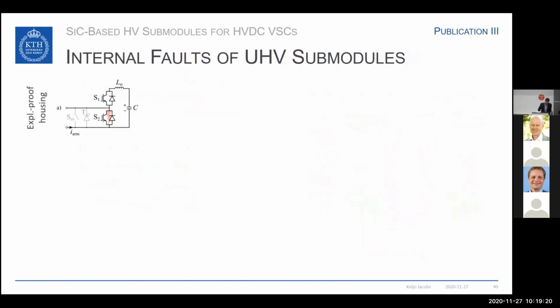For those conventional submodules, we would employ an explosion-proof housing, and I'm going to explain this step by step here. For example, here I use the example of a half bridge, and if switch 2 fails and we turn on switch 1, we get a discharge of our capacitor through the half bridge. The arm current will be conducted through the bypass equipment, which can be thyristors and mechanical switches. However, the energy discharge from the capacitor will destroy those modules and lead to an explosion. And therefore, we need explosion-proof housing for such devices, for such submodules.